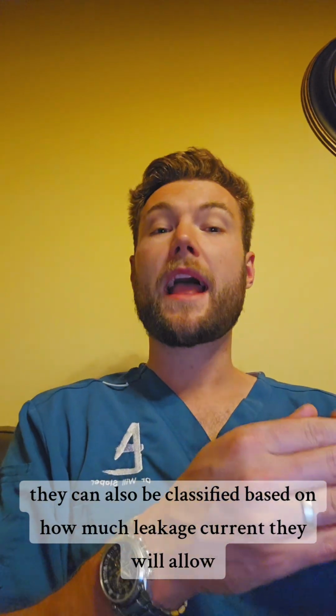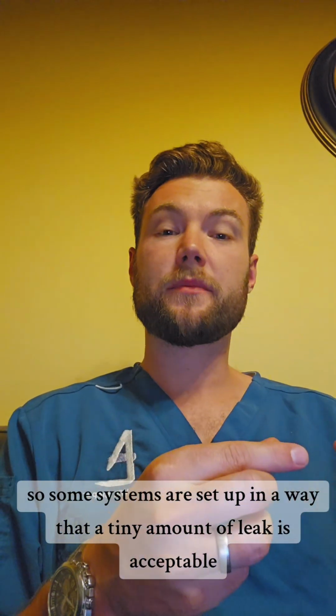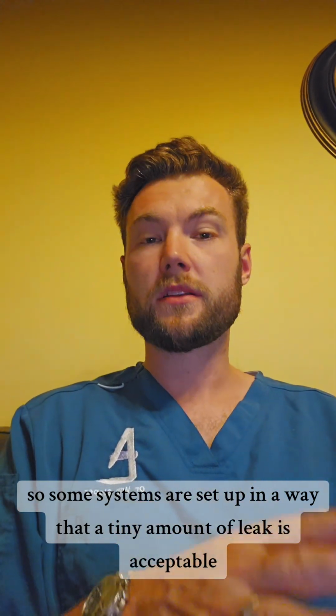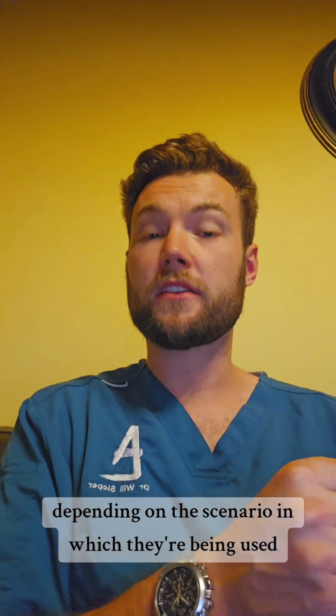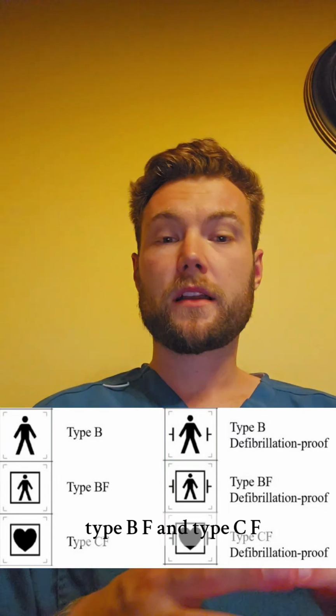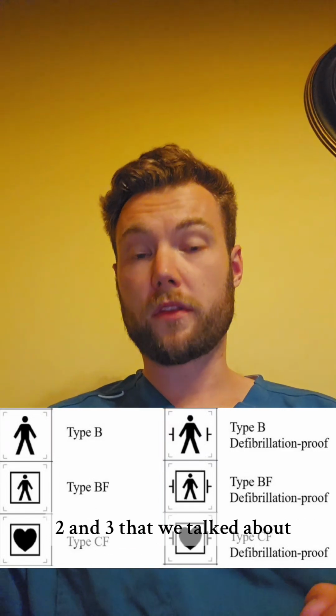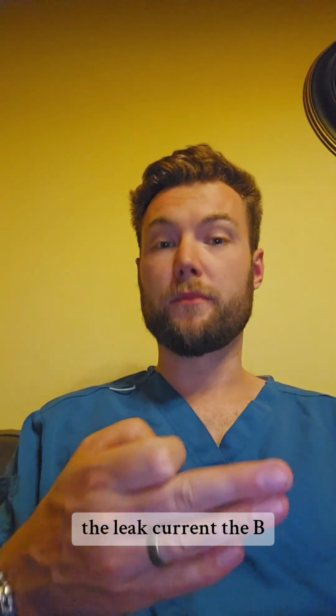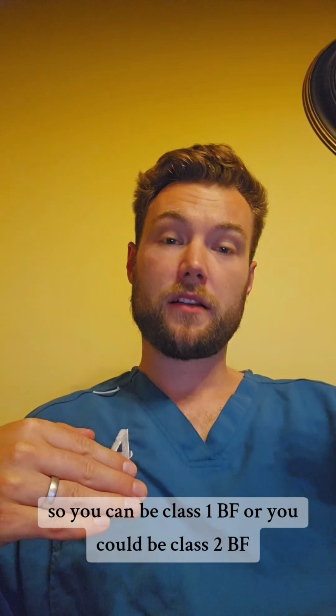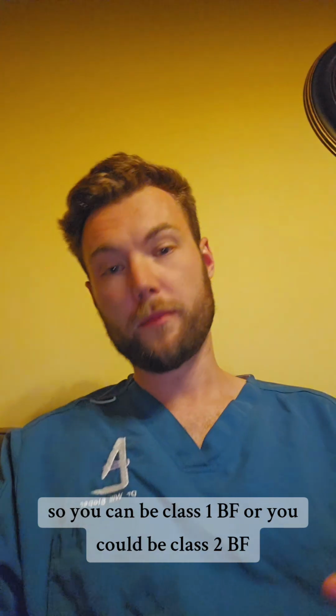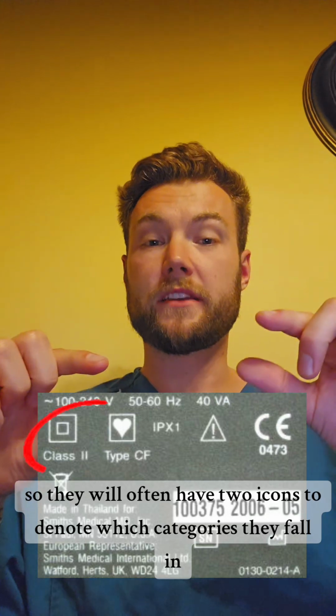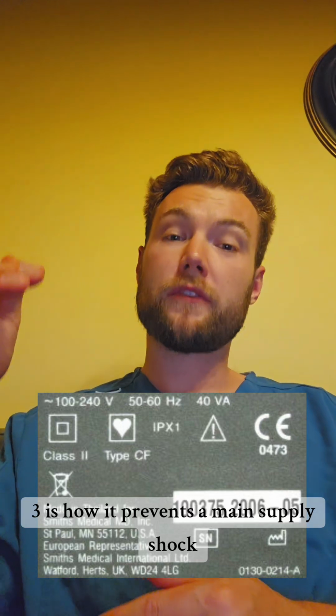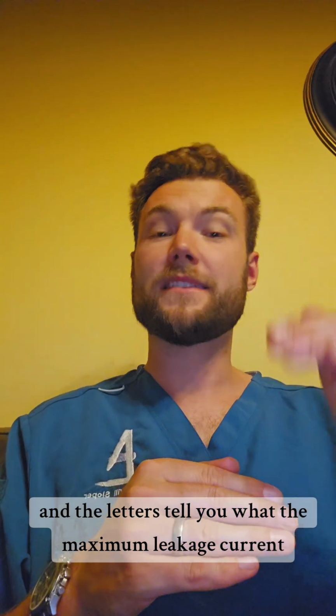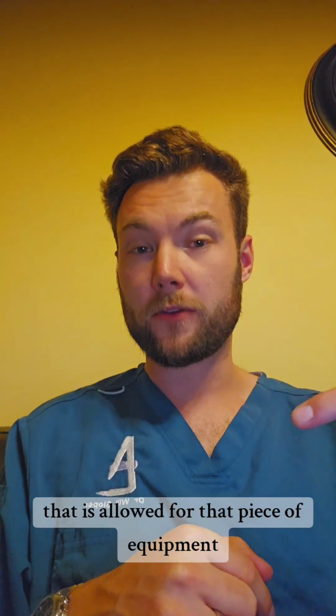They can also be classified based on how much leakage current they will allow. So some systems are set up in a way that a tiny amount of leak is acceptable, depending on the scenario, but they are classified differently depending on the scenario in which they're being used. And there are 3 types you need to be able to name. They're type B, type BF, and type CF. And this is a separate classification from the class 1, 2, and 3 that we talked about with regards to whether they're double insulated, earthed, or just really low voltage. The leak current, the B, BF, CF, is a separate classification. So you can be class 1 BF, or you could be class 2 BF. So they will often have 2 icons to denote which categories they fall in. The thing to know is the 1, 2, 3 is how it prevents a mains supply shock, and the letters tell you what the maximum leakage current that is allowed for that piece of equipment.